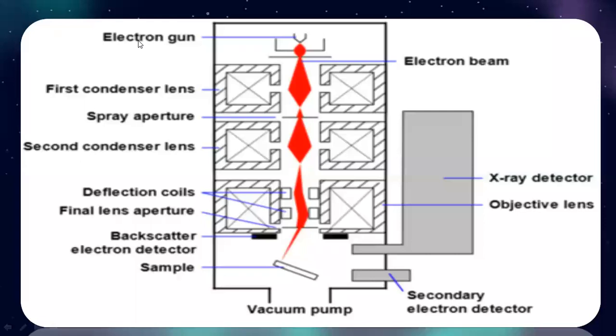This is a diagram of the scanning electron microscope. The electron gun consists of cathode and anode. The condenser lens controls the amount of electrons traveling down the column. The objective lens focuses the beam into a spot on the sample. The deflection coil helps to deflect the electron beam as it attracts secondary electrons. Additional sensors detect backscattered electrons and X-rays.